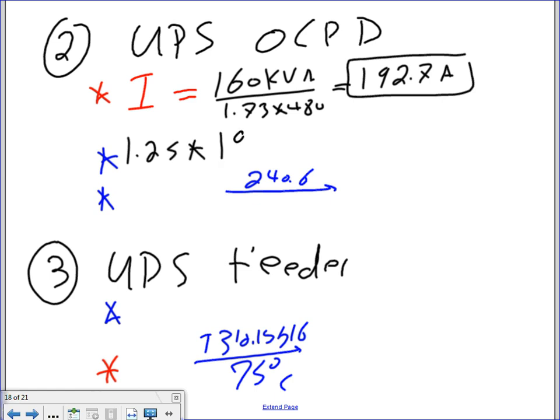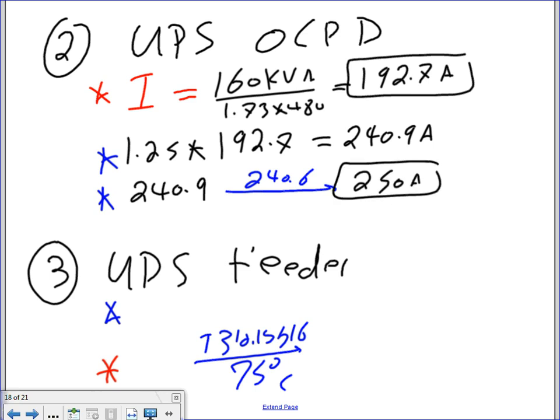Multiply this by 192.7, and what do you guys come up with? 240.8. 240.9 amps, something around this number. And then you're going to take the 240.9 next, and that will give me 250. Right? I have 250. Can somebody verify? Yeah. I have 250. So my overcurrent protection device on the primary side is going to be a 250 amp circuit breaker. 250.